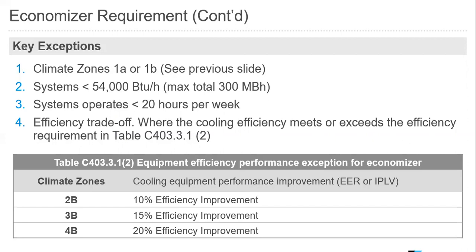While you're on that slide, Corey, I'm sorry to interrupt, but just for the code officials on here, this is a major headache. Climate zone 2B, a dry climate zone 2 is what B is, so we don't have to have an economizer. We can have more efficient equipment there, where it's typically more appealing to bring in dry outdoor air, whereas in Houston, climate zone 2A, you can't use more efficient equipment in lieu of an economizer, which is broken in the 2015 Energy Code. They have fixed this in the 2018 Energy Code. It no longer specifies B.